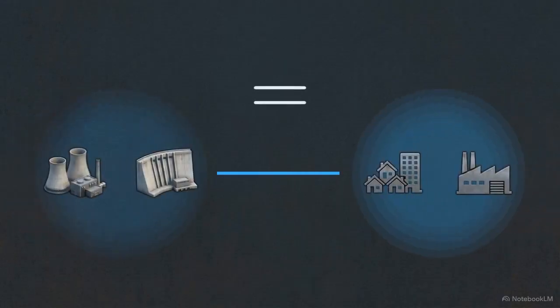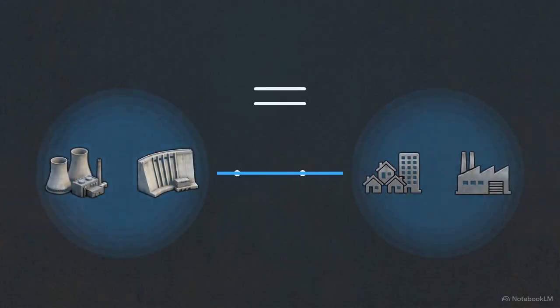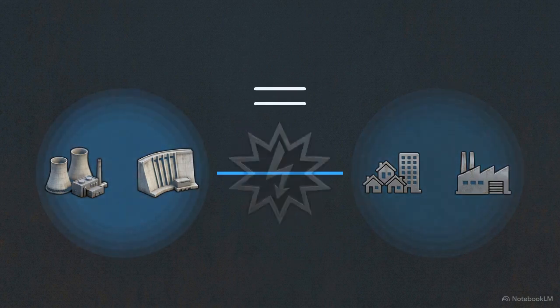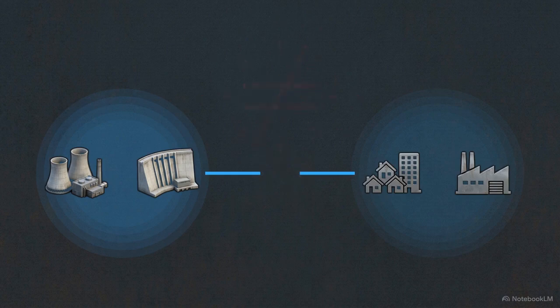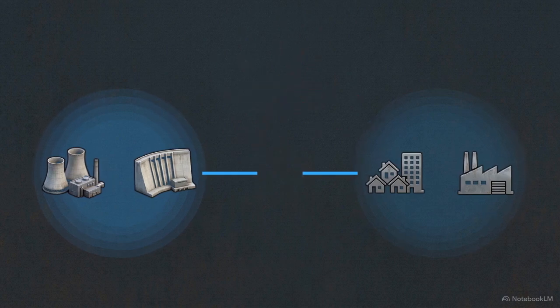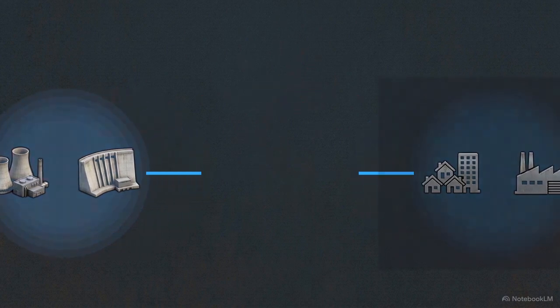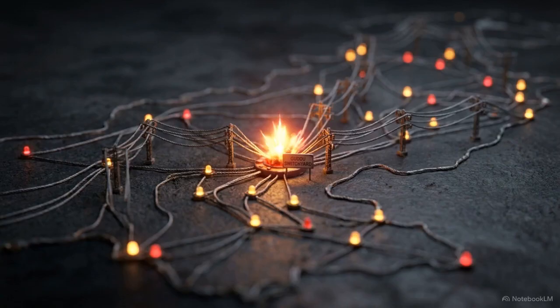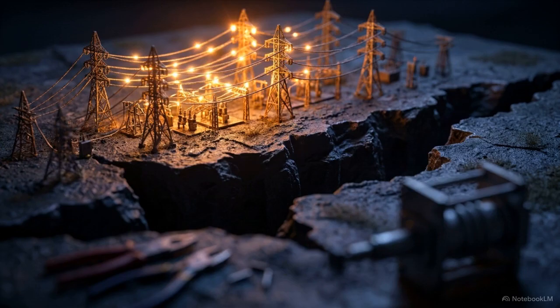The power grid is governed by one non-negotiable law. Generation must exactly equal demand every second, or the system begins to fail. When critical transmission corridors are lost, the national grid violently fractures into disconnected zones called islands. In January 2021, an error at Pakistan's Guddu switchyard created an unstable power swing and instantly severed the country. The north was left with too much generation, while the south was left with a massive deficit.